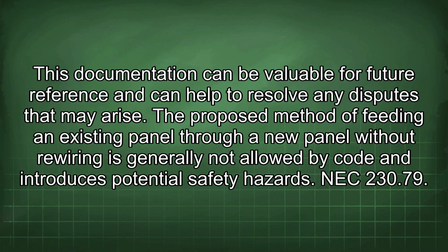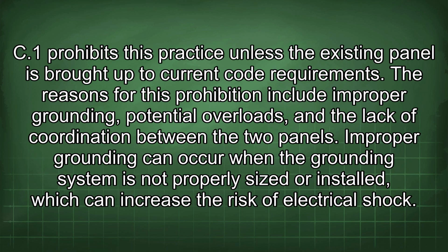This documentation can be valuable for future reference and can help to resolve any disputes that may arise. The proposed method of feeding an existing panel through a new panel without rewiring is generally not allowed by code and introduces potential safety hazards. NEC 230.79 C1 prohibits this practice unless the existing panel is brought up to current code requirements.